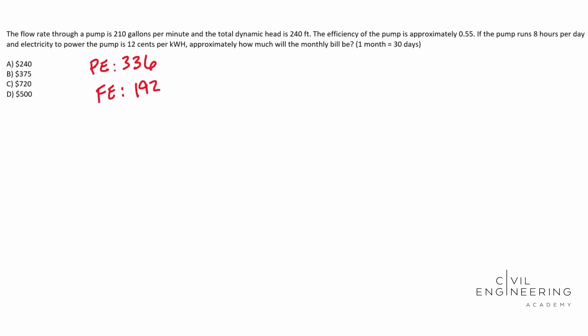So you'll notice a discrepancy between these two formulas. In the PE, it gives you BHP is equal to our flow rate times our gamma times our head over 550 times N times our efficiency of our pump.